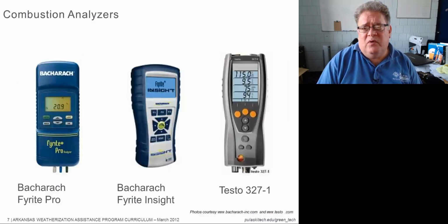And then when it comes to combustion equipment, we want to have a good combustion analyzer. Now there are a lot of good ones. You can go from a very basic like this Bacharach Fyrite Pro, which has been around for a long time. It's still available. The Bacharach Insight, and they're making a couple of models of those. And then the Testo over here is another really good example of a very powerful, this 327 is a very powerful and capable instrument, and so is the Insight. I'm not going to recommend one over the other, but even at that, the Bacharach Fyrite Pro will do a very good job. The biggest thing here that you want to do is make sure that you get one that has 2 sensors in it that can detect 2 types of gases, preferably oxygen and CO.